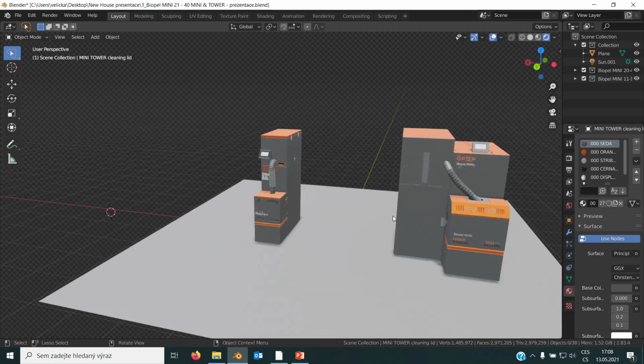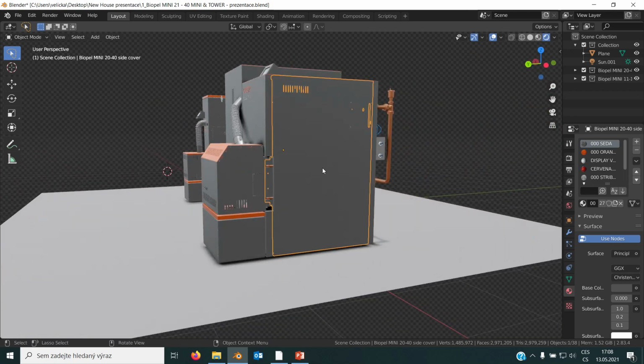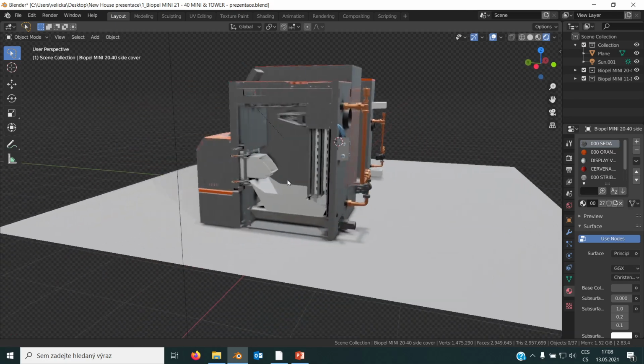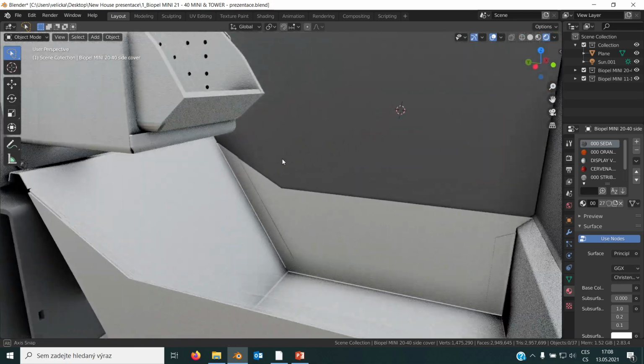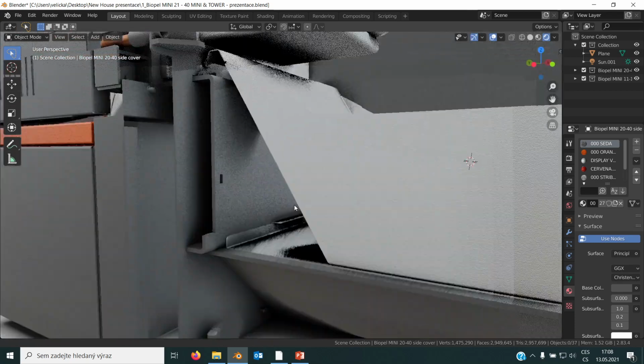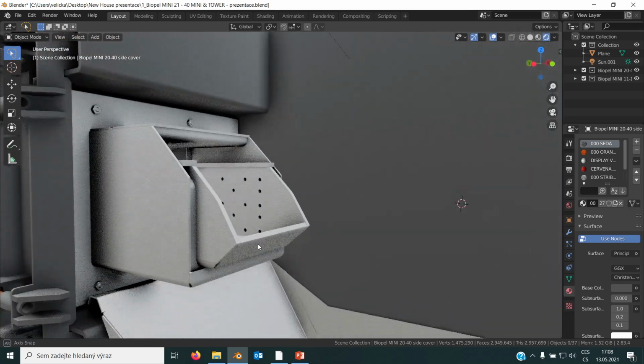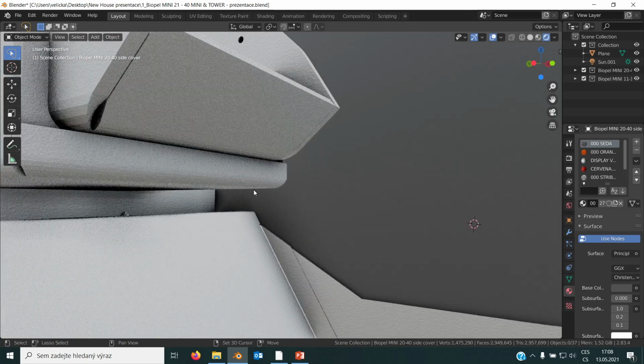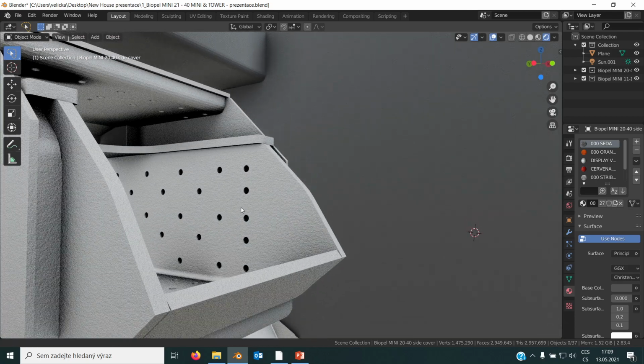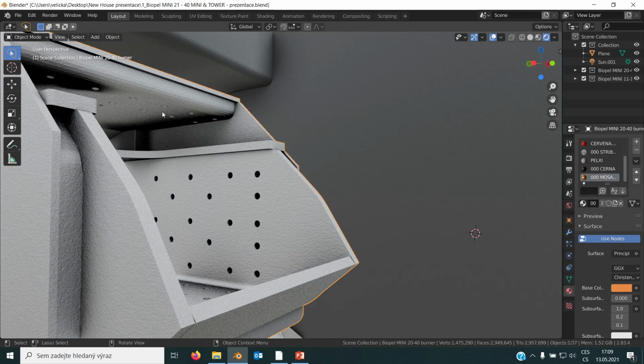Yeah, so speaking of the burner, the last thing I think I didn't mention is the difference on the burner in the front, because I told you that the boiler has slightly better emissions, and the reason for that is also that we implemented secondary air here. So normally inside the burner grate there are holes for the air to create good combustion, and right now we also have secondary air which comes from the top, which makes the burning process better.